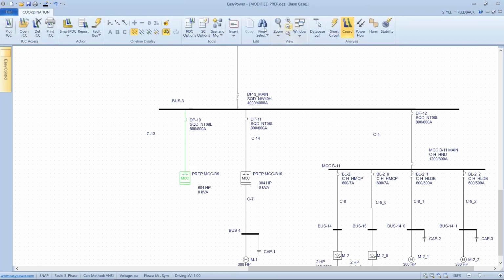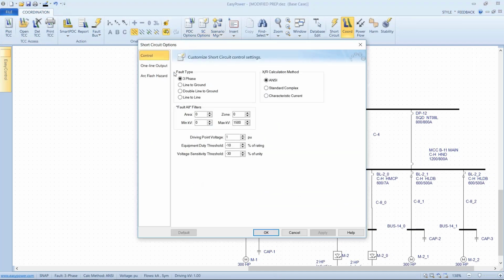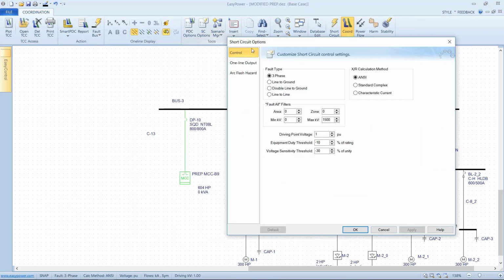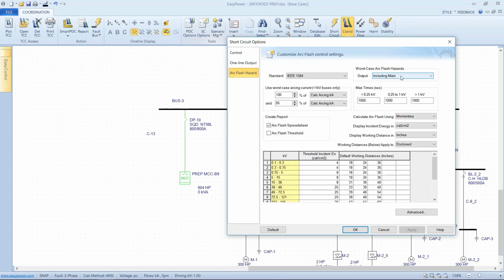When we're in short circuit focus, the short circuit options allow us to set either including main or excluding main. So this is a decision that needs to be made regarding the motor control center itself. If there is an arc flash barrier between the main and the main bus, then we can use including main. If there's not, then we have to exclude main, in which case we'd be dependent upon the next upstream breaker.